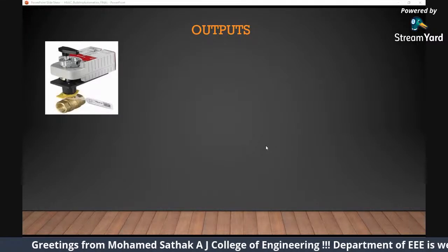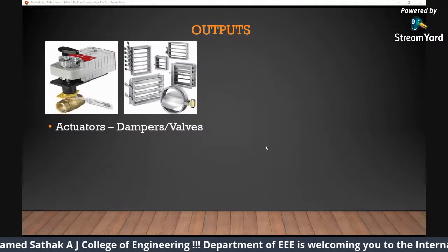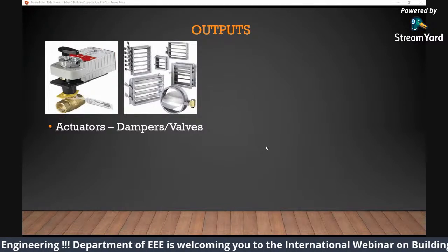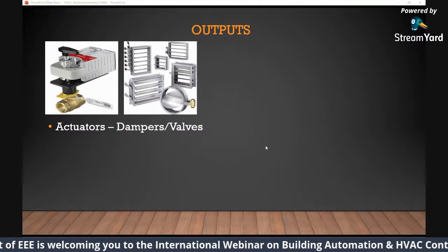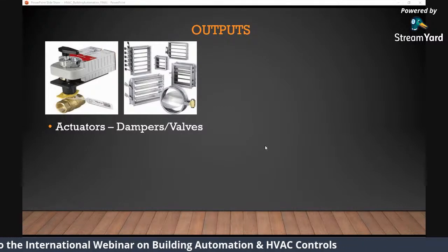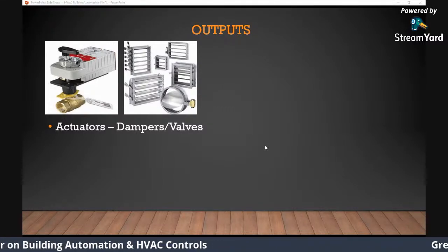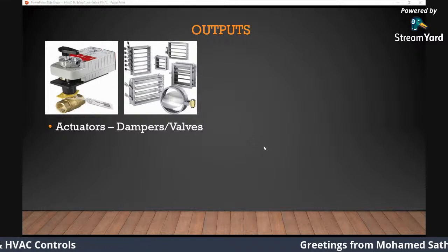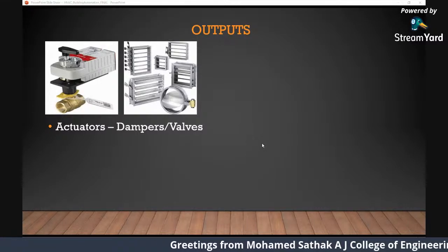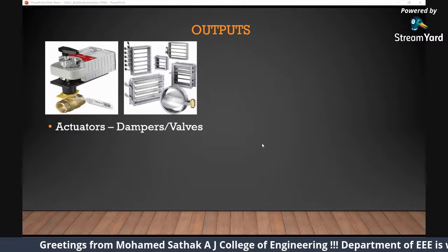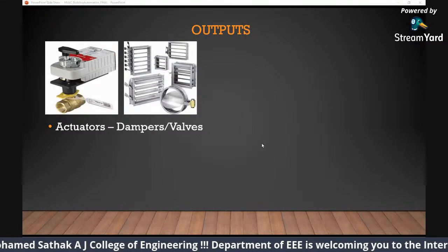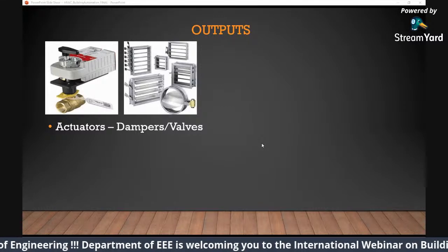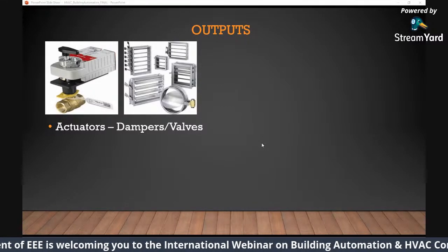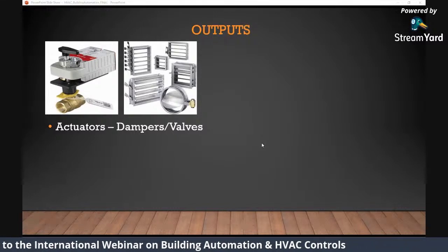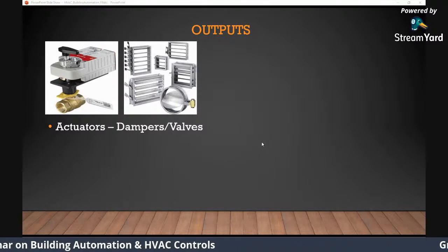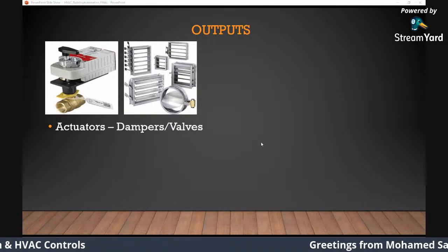So, what are the different outputs we come across? Actuators, we call them actuators. Again, your dampers and valves are your mechanical equipment. So what is the electrical equipment which controls your dampers and valves? Okay, so actuators are the ones which control your dampers and valves. Let's say you want to open a window, you go and open the window manually. What if you put a motor or actuator on a window and you send a command signal from a controller to the window? So that's the purpose of an actuator. Let's say it's too hot outside, you need natural outside air. So the controller senses the temperature in the room and it automatically sends a command to the actuator, and the actuator opens your window. So that's the complete concept behind it.